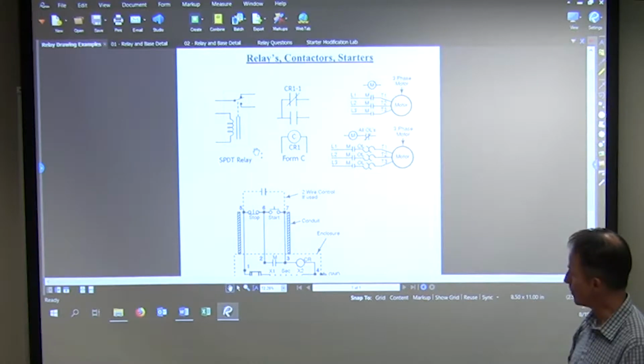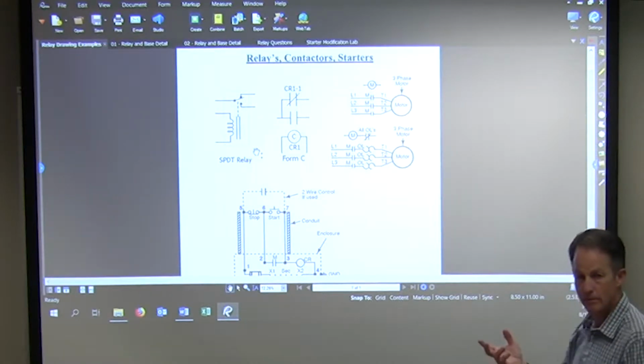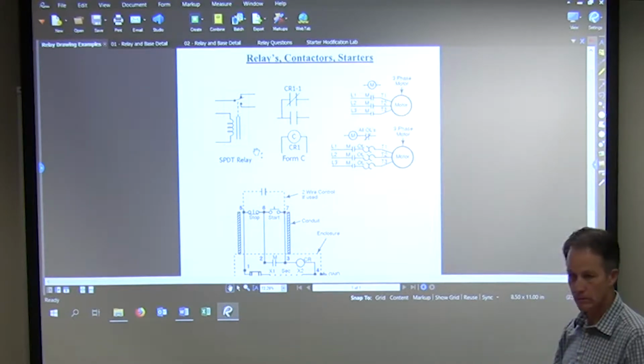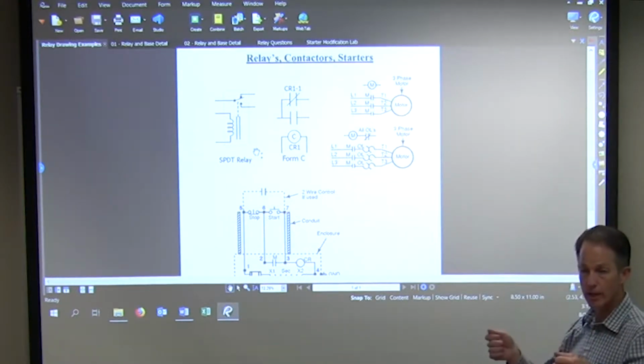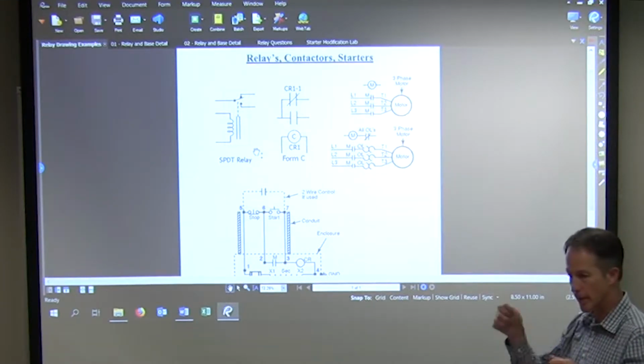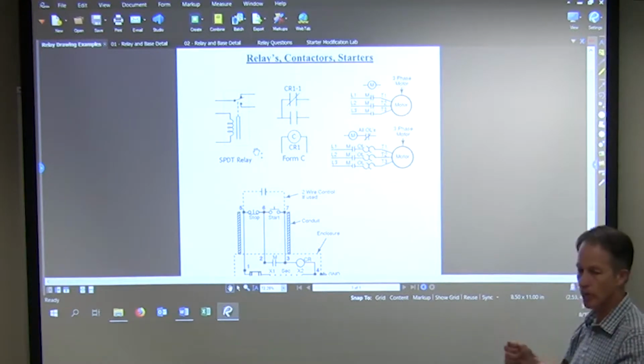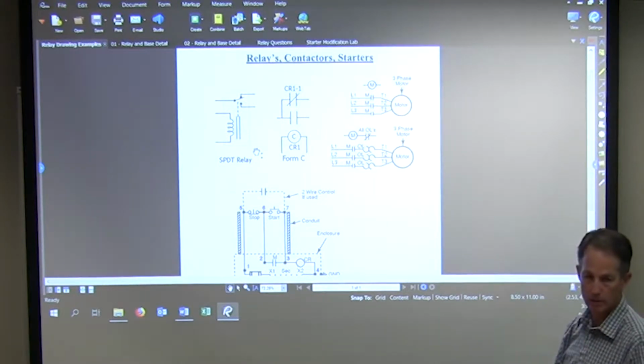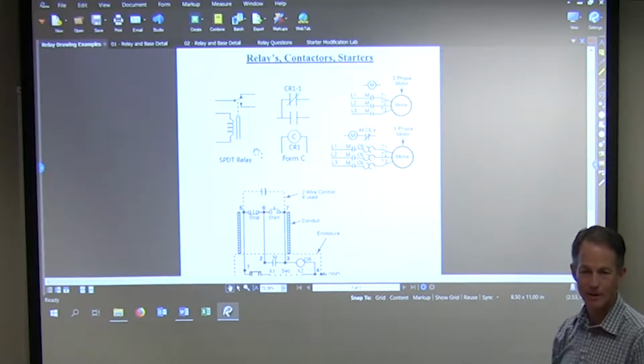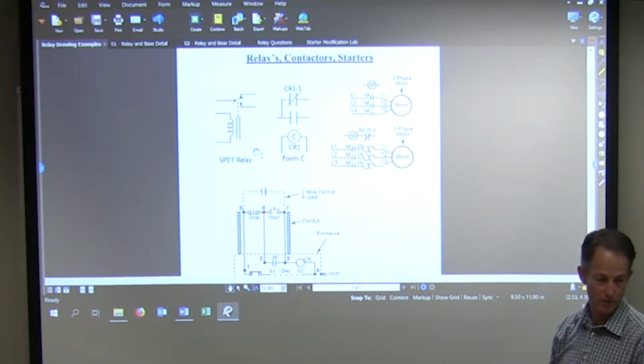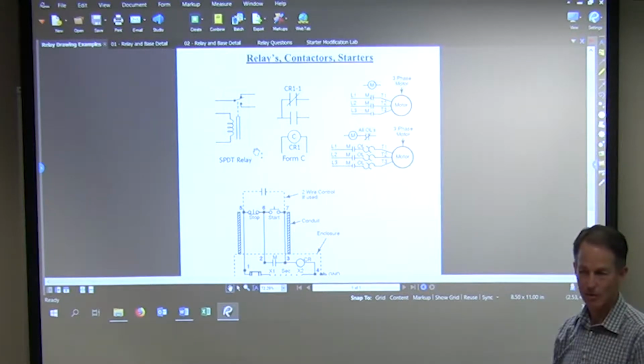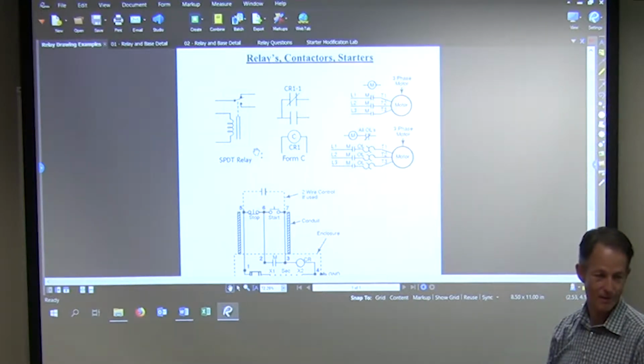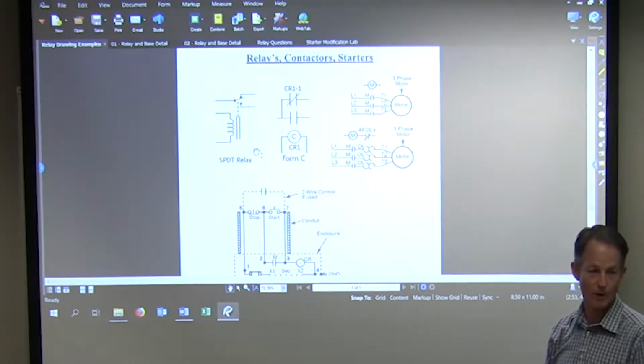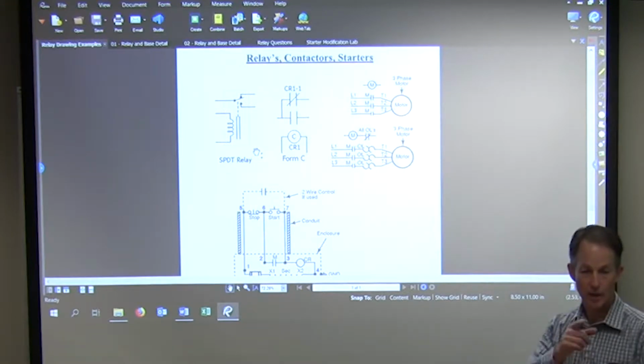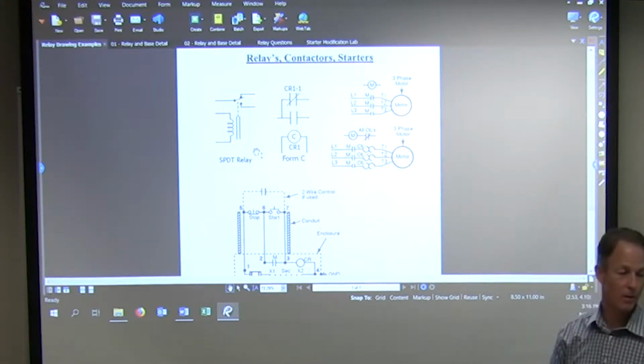So put it on 24 volts. What should I see, and how do I measure it? It's energized, 24 volts. So I'm going to put my leads one on either side of the coil connection, right? And I should see that across. What if I see 24 volts across the coil, but the coil's not working? If there's current going through it, you would not get 24 volts. Ah, there we go. Okay. What will I get across it? Hopefully 0, or very low voltage. Are you sure? Actually, no. You will see 24 volts across the coil, but not across the contacts, right? Because remember, it's a load.